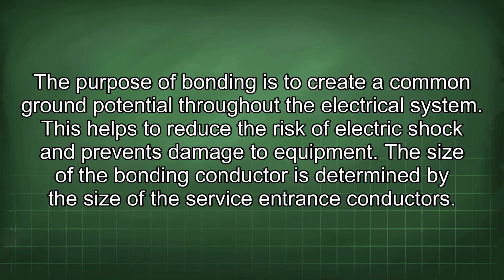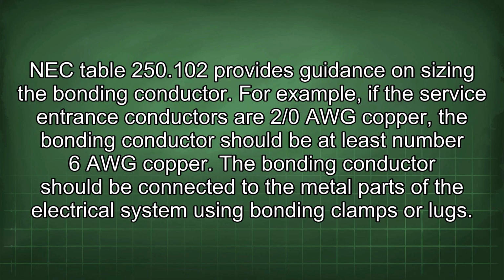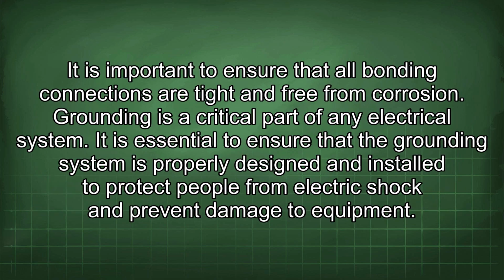The size of the bonding conductor is determined by the size of the service entrance conductors. NEC Table 250.102 provides guidance on sizing the bonding conductor. For example, if the service entrance conductors are 2/0 AWG copper, the bonding conductor should be at least number 6 AWG copper. The bonding conductor should be connected to the metal parts of the electrical system using bonding clamps or lugs. It is important to ensure that all bonding connections are tight and free from corrosion.